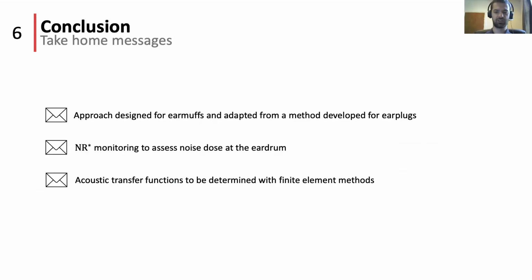What you may retain from all this are the following. First, our proposed approach was adapted from a method developed for earplugs. Second, the noise reduction monitoring can be used to estimate the noise dose at the eardrum, thus mitigating the contribution of the wearer-induced disturbances and the difficulty to place microphones under the earmuff. And third, the transfer functions can be assessed with the finite element method.